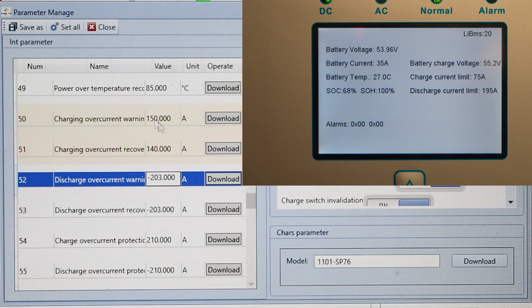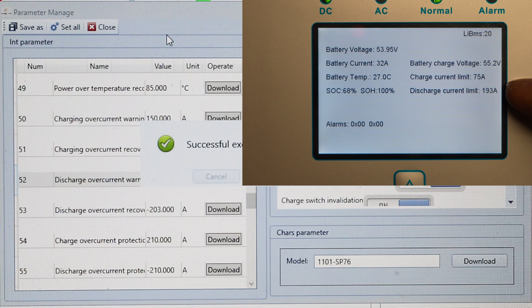The discharge current limit comes from item number 52, and for some random reason it just seems to be 10 below whatever that figure is, the discharge over current warning, I think it is. So I can't change it lower than 203 at the moment without changing the next line down. So if I change that down to 203 and set that, you can see that goes to 193.